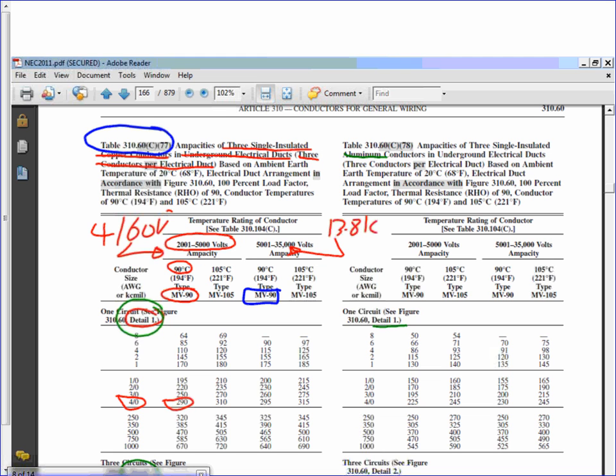None of you probably have ever been here. The first thing you need to pay attention to is the voltage. The voltage here goes up to 5,000 volt. The second set of columns goes up to 35,000 volt. So if your system is 13,800, you're here. If your system, like the one that we're using, is 4160, I'm right in here. Everybody knows why I went there? Then I have 2 options: either MV 90 or 105. What's your default? Unless you know otherwise, 90. So we go to the MV 90, and then here's my amps, and here's my conductor. Why didn't I go to this side? Anybody? Because my voltage is not within that range of 5,001 to 35,000. You're going to go where your voltage range is.